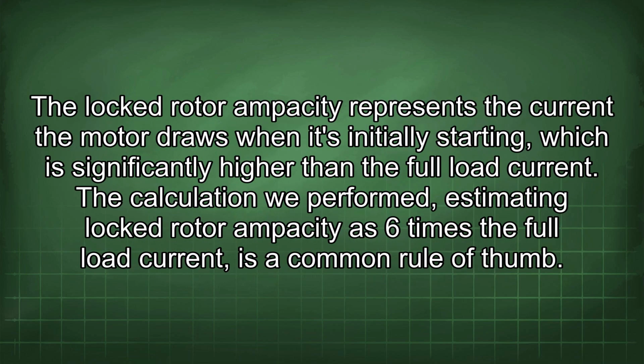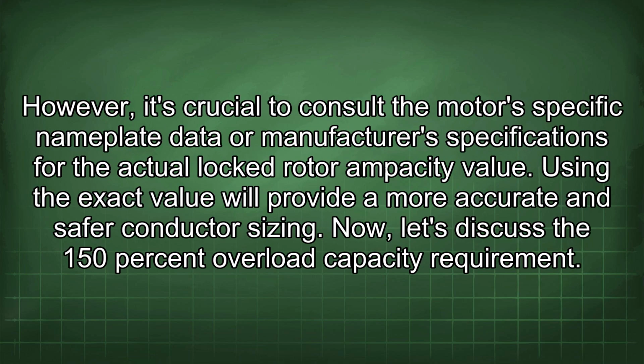The locked rotor ampacity represents the current the motor draws when it's initially starting, which is significantly higher than the full load current. The calculation we performed, estimating locked rotor ampacity as 6 times the full load current, is a common rule of thumb. However, it's crucial to consult the motor's specific nameplate data or manufacturer's specifications for the actual locked rotor ampacity value. Using the exact value will provide a more accurate and safer conductor sizing.